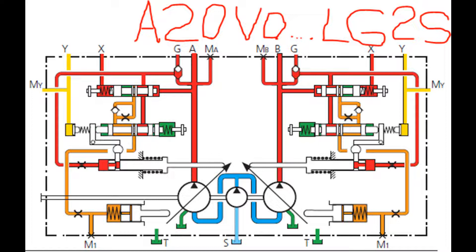LR Power Control with Stroke Limiter: The stroke limiter can be used to vary or limit the displacement of the pump continuously over the whole control range. The displacement is set in LRH with the pilot pressure PST, maximum 40 bar, applied to port Y; or in LRU by the control current applied to the proportional solenoid. A DC current of 12V (U1) or 24V (U2) is required to control the proportional solenoid.